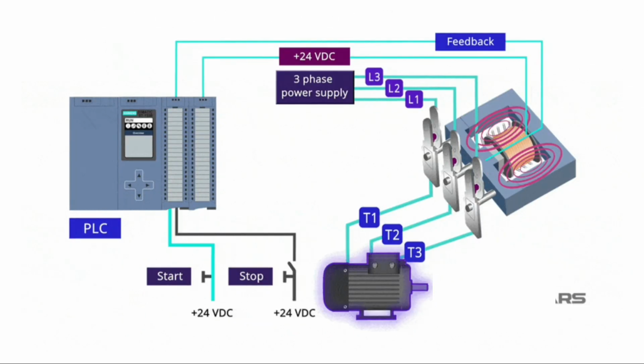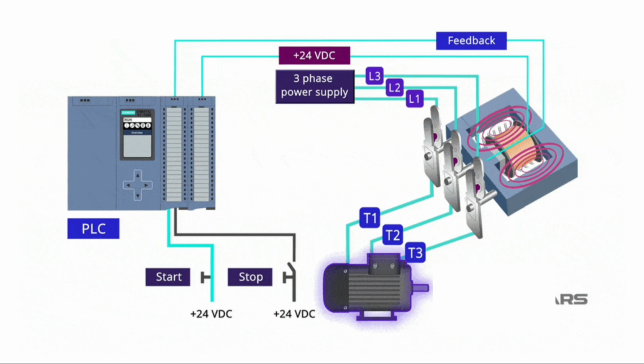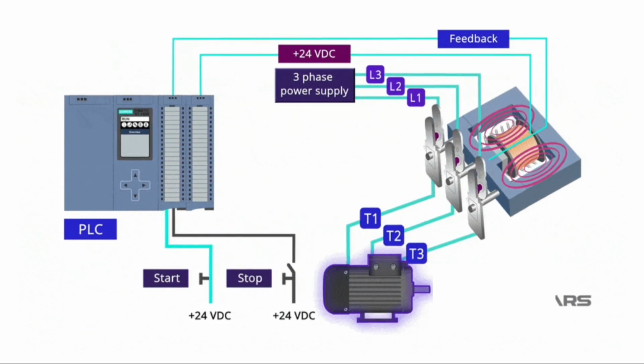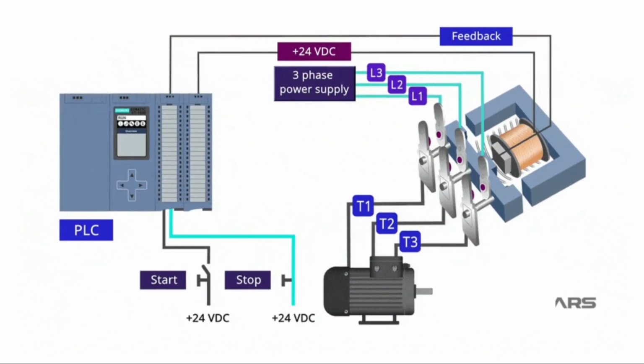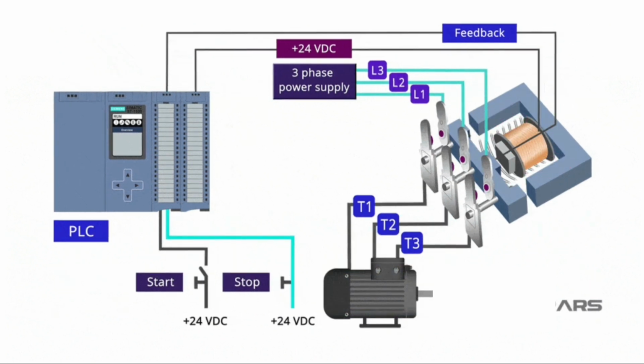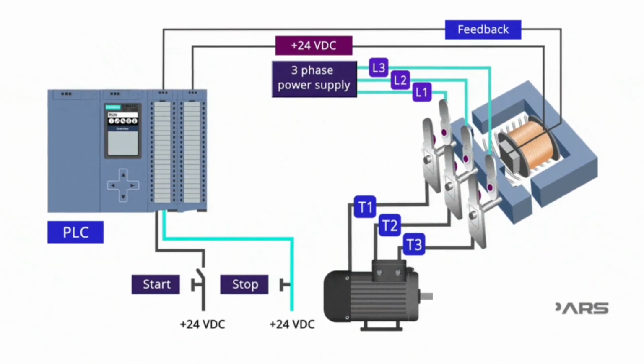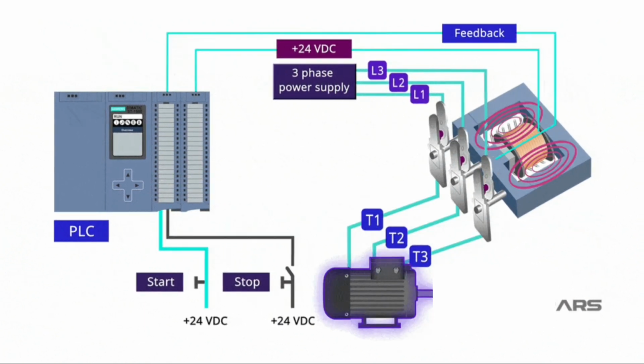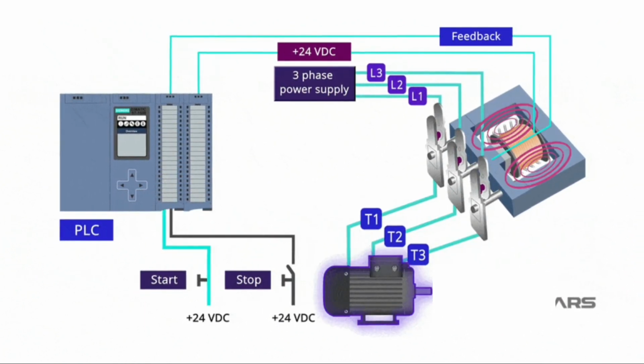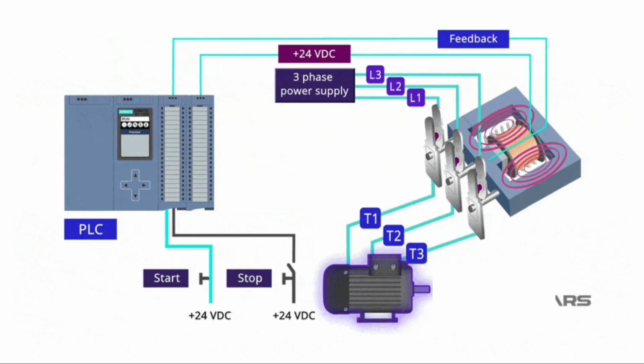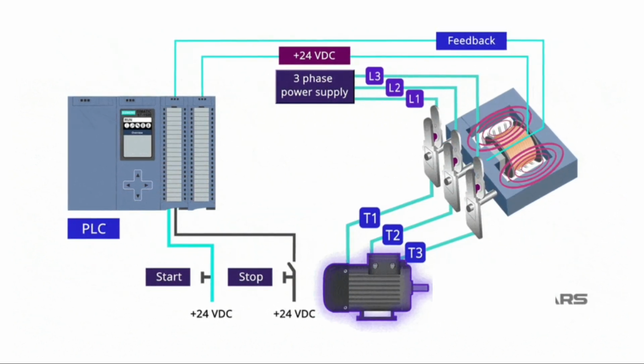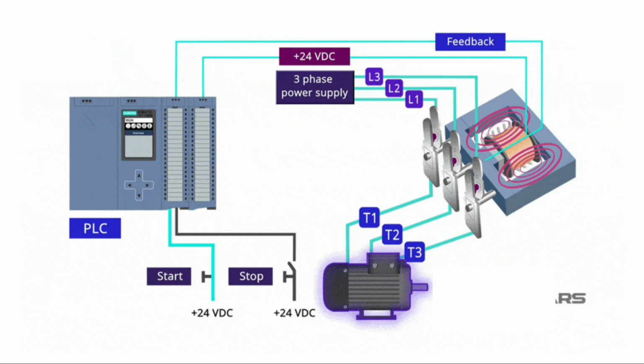You also need a start and stop switch to be connected to the PLC input. This way, when you press the start switch, the coil will be energized, the contacts will be closed and the motor will be turned on. When this happens, the feedback contact will be closed as well and a signal will be sent to the PLC input, telling us that the contactor is working properly. When you press the stop switch, the coil will be de-energized, the contact will open and the motor will turn off.